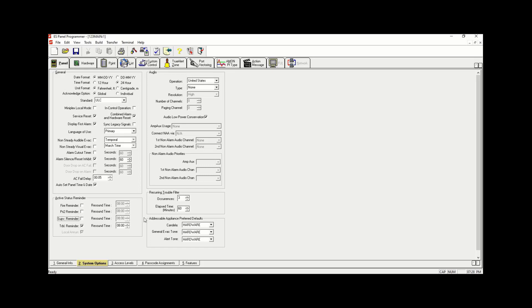Under Reoccurring Trouble we're going to leave it as zero. What is a reoccurring trouble filter? Basically, if there is a reoccurring identical trouble — three of them within one 60-minute period — the panel will automatically activate a latching reoccurring trouble filter on the panel. The only way to reset it is by clicking System Reset.